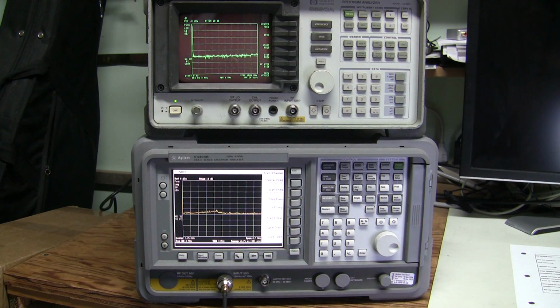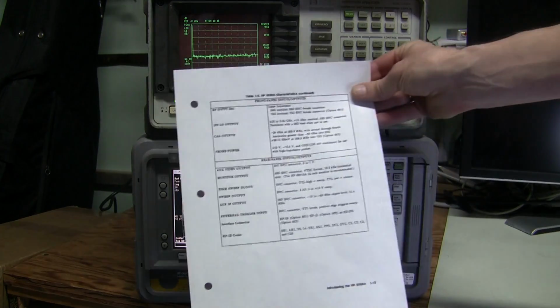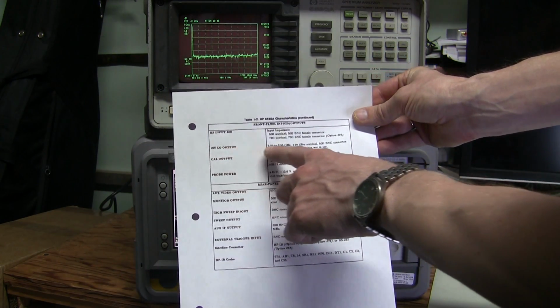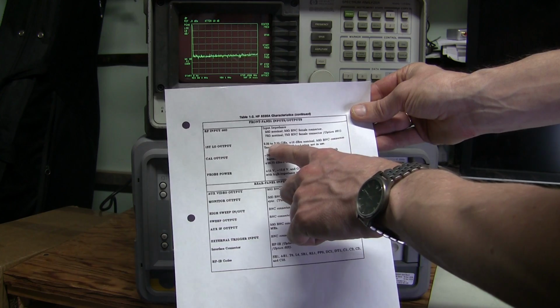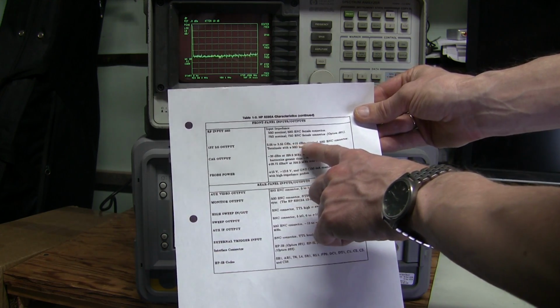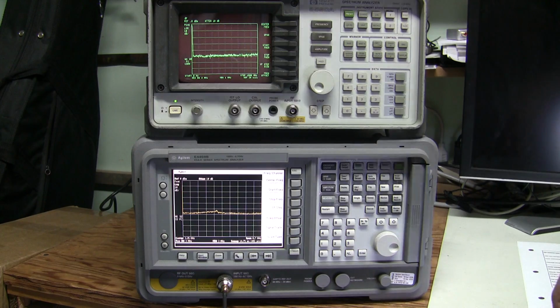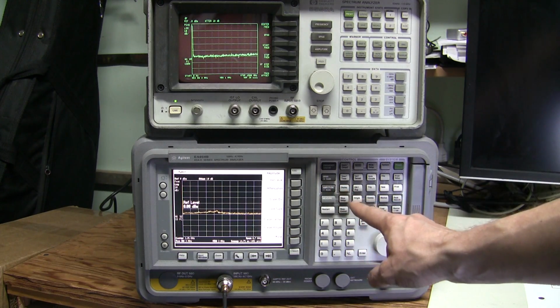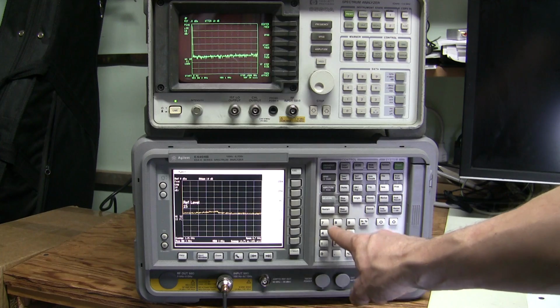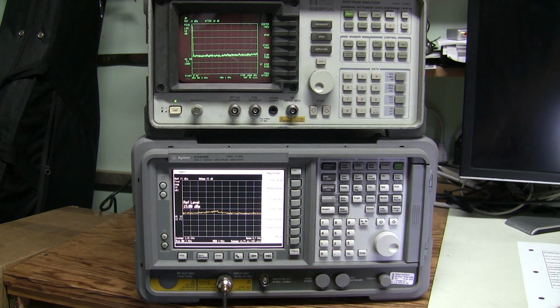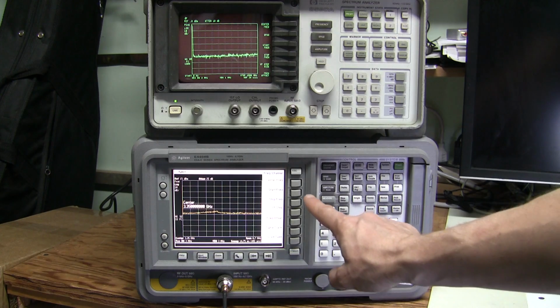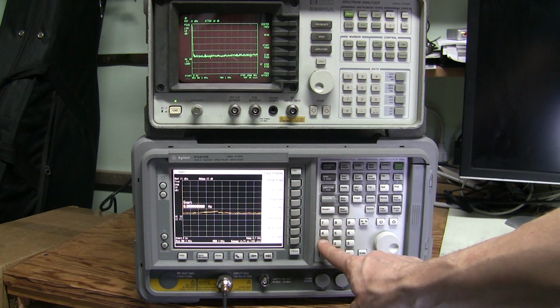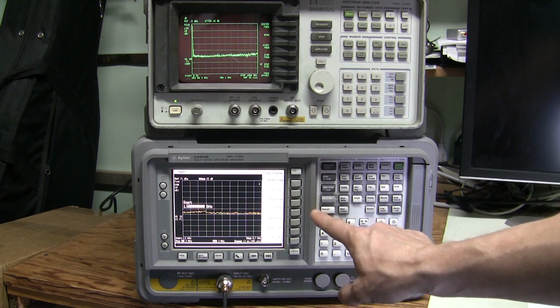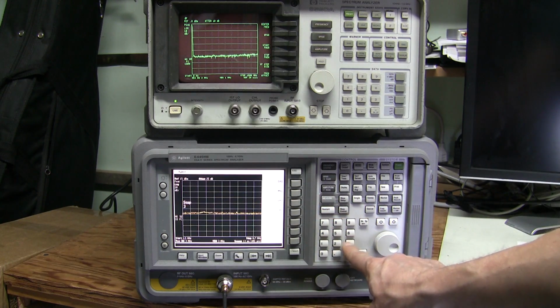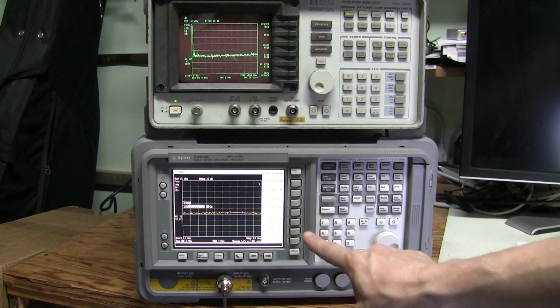So we should see on the first LO output from 2.05 to 3.55 gigahertz plus 10 dBm. Now let's set this analyzer amplitude slightly higher, 15 dBm let's say, and the frequency range slightly wider than we need. Let's start from 1.5 gig and stop at, let's say, 3.8 gig. And now we can connect the first LO.